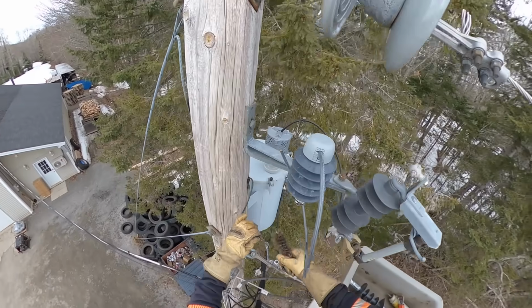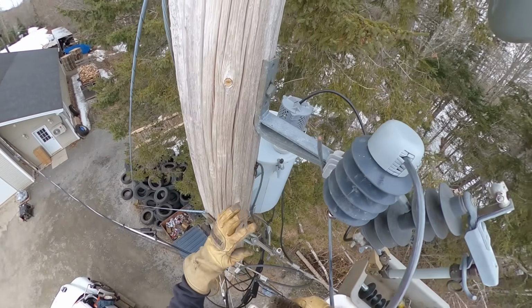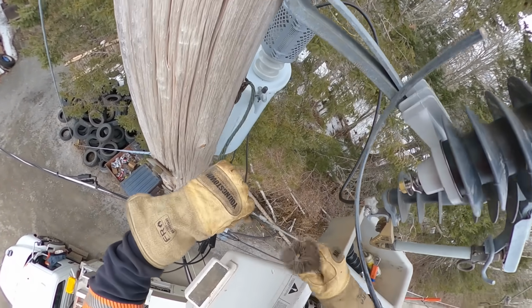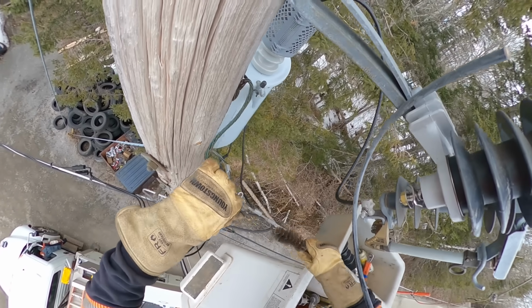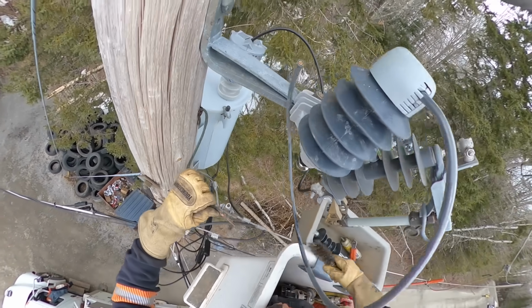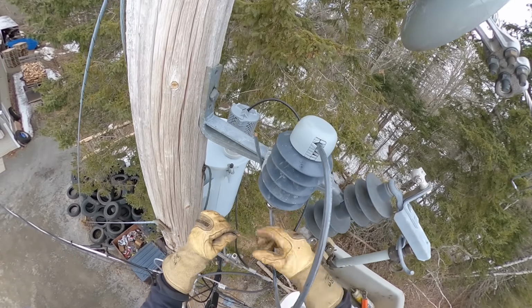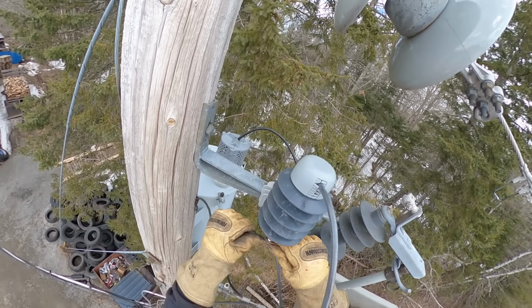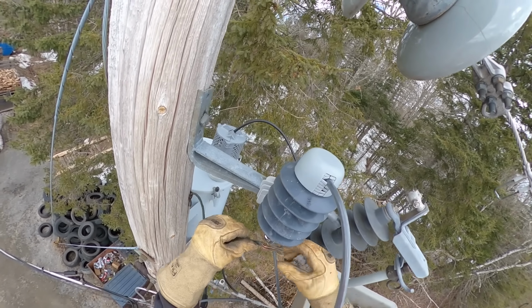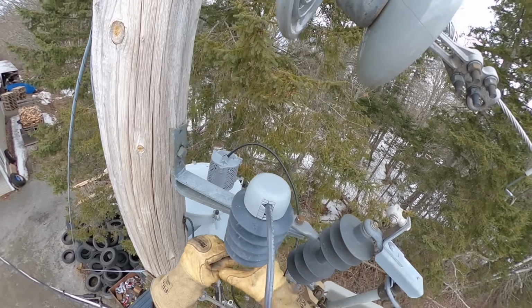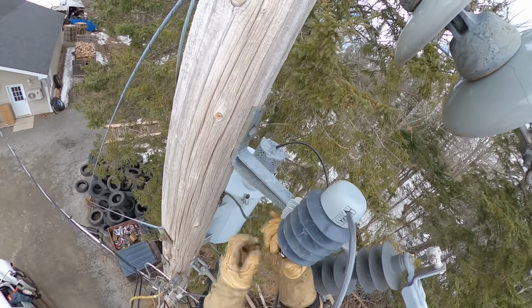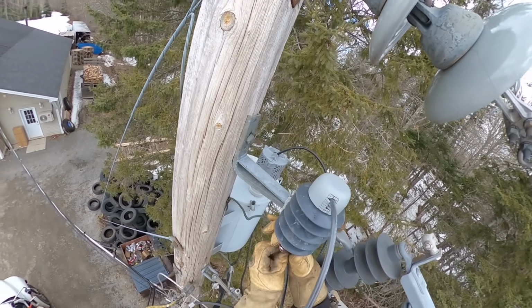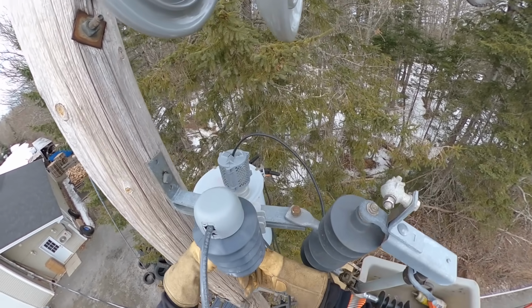Now on the butt ground, the pole ground side of things, you could see how corroded that is. There's lots of oxidation. It's pretty green. You don't want to plug that back in as is. You really want to shine up that copper so it makes a good connection on the bottom of the lightning arrestor, or any connection for that matter. Whenever you're making connections on existing wire that's in the air and it's corroded, even aluminum, you want to shine that up to make a good connection.